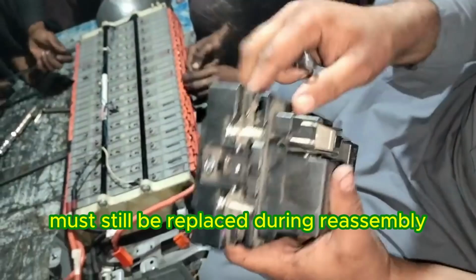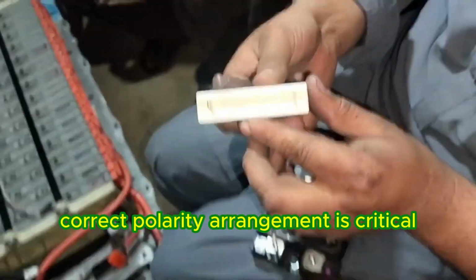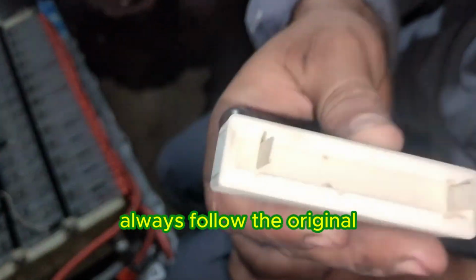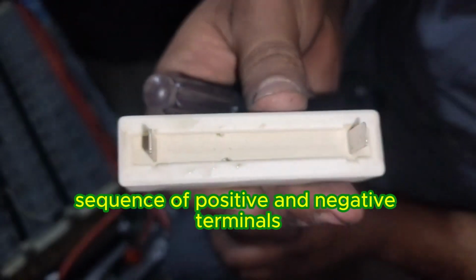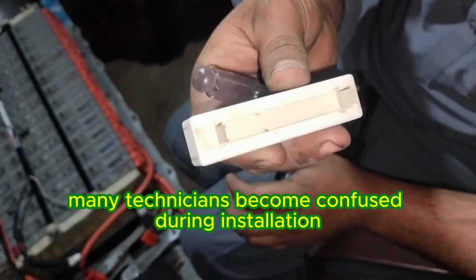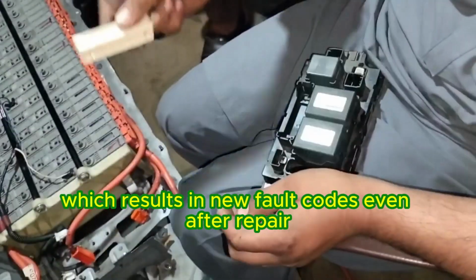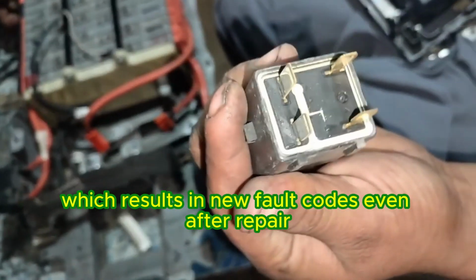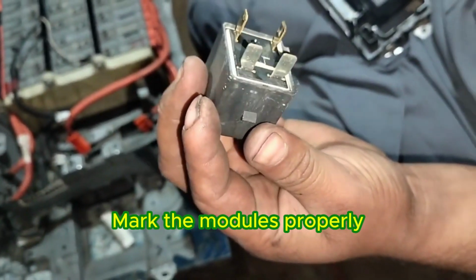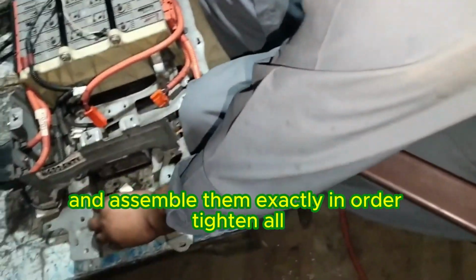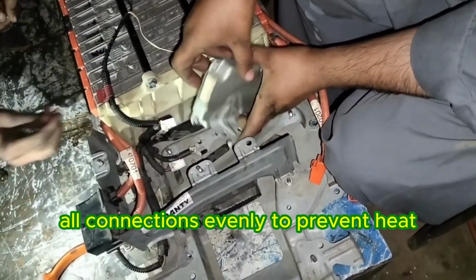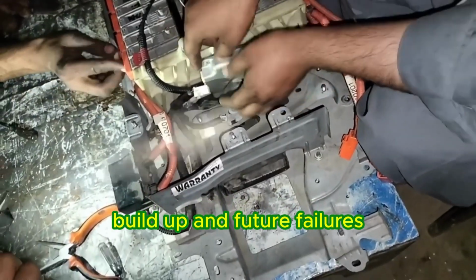During reassembly, correct polarity arrangement is critical. Always follow the original sequence of positive and negative terminals. Many technicians become confused during installation, which results in new fault codes even after repair. Mark the modules properly and assemble them exactly in order. Tighten all connections evenly to prevent heat buildup and future failures.